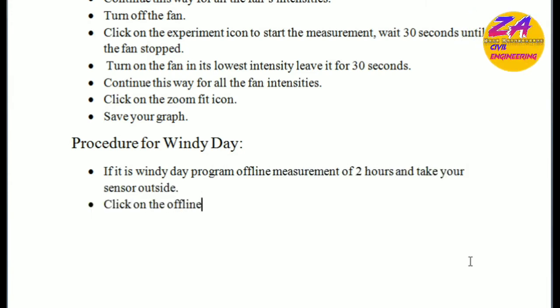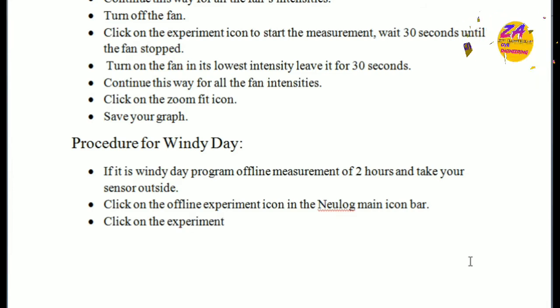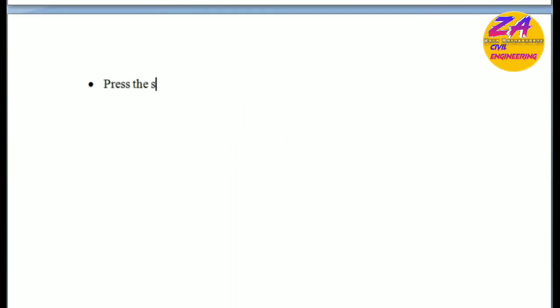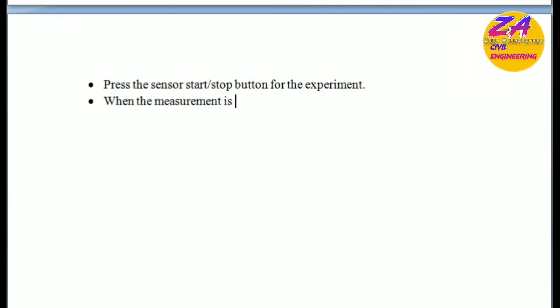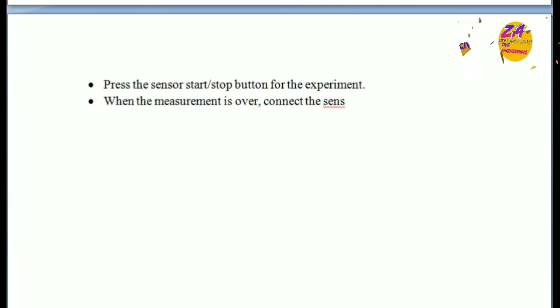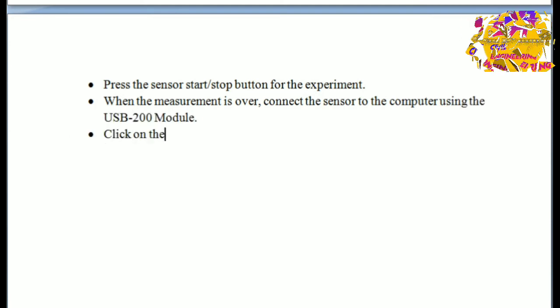For a windy day, program an offline measurement of two hours and take your sensor outside. Click on the offline experiment icon in the Neulog main icon bar. Click on the experiment setup icon and set the time and duration. Put the sensor in a stable place and press the sensor start/stop button to begin the experiment.